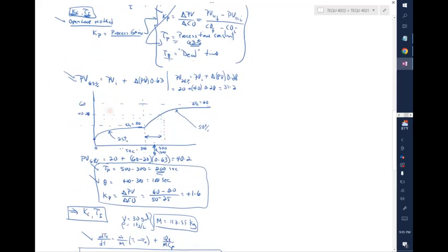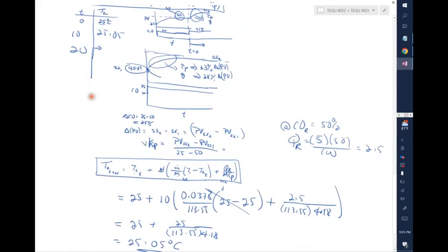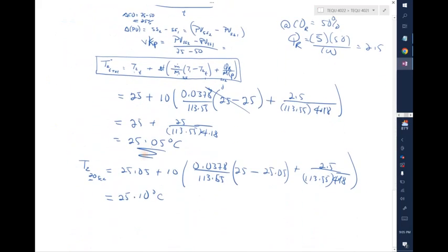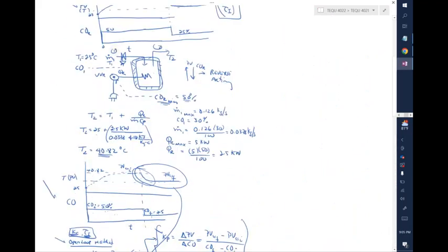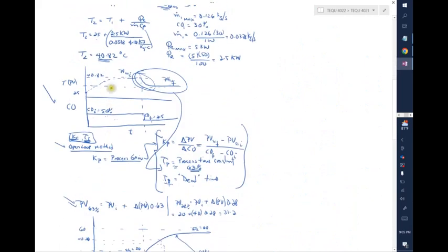So the only thing left now is to go to Excel and try to get this dynamic curve, at least this one is the one that I'm interested in, because it's the one that I propose in order to get Kp, tau p, and theta. I'm gonna call from now on theta just to avoid confusion. It's dead time. How much dead time this process has. So I'm using the 28% calculation.